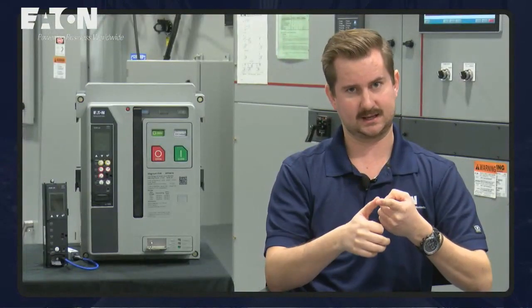Okay, great. So how about other features like zone selective interlocking? Any improvements to that from what we had in Digitrip? Yeah, so for zone selective interlocking, I'm just going to call that ZSI for short. One of the cool things we were able to do is, on the trip unit display, we have an indication that allows you to see whether ZSI is disabled, enabled, and if it's active and actually working.